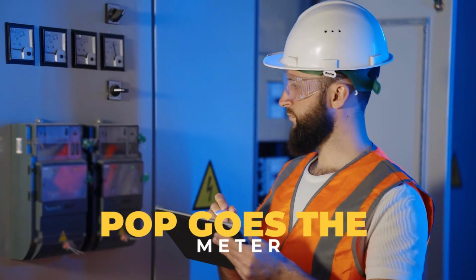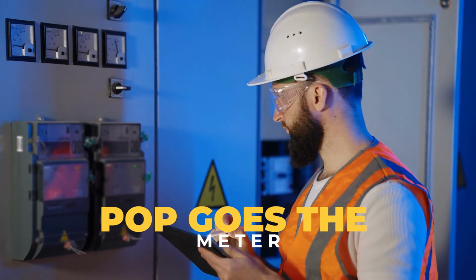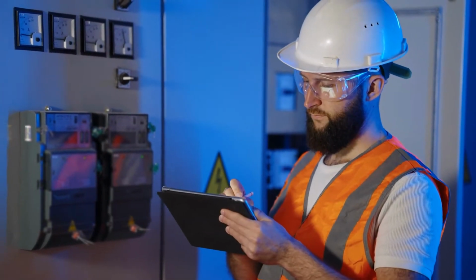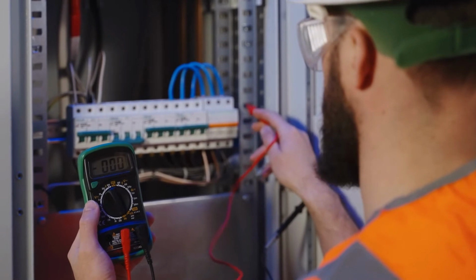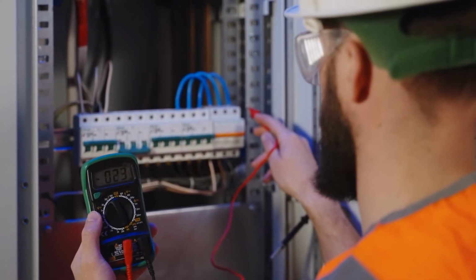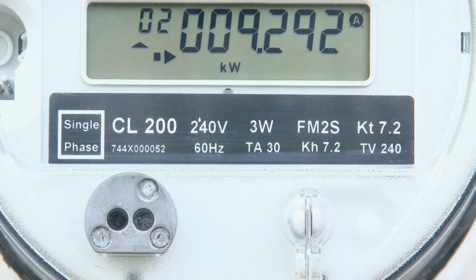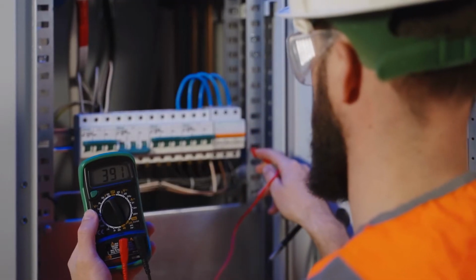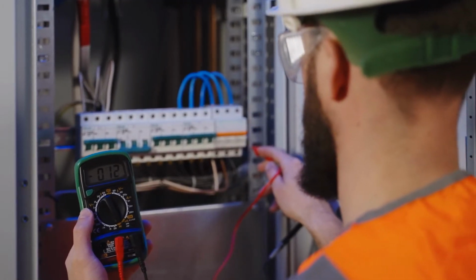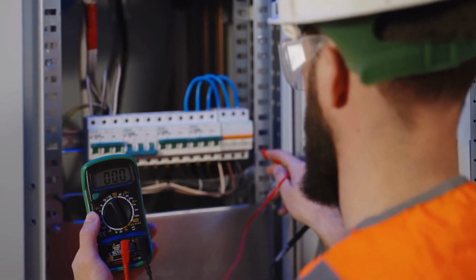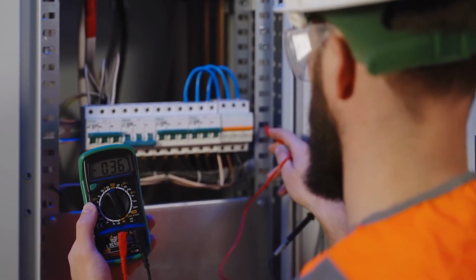Pop goes the meter. What's the most common electrical measuring error these experts have come across? The winner is a small family of faults, all of which stem from incorrectly configuring the digital multimeter, DMM. An electrical safety inspector based out of Canada described it as switching from volts range to current range on the multimeter with leads still attached.